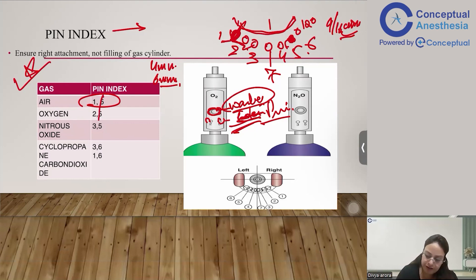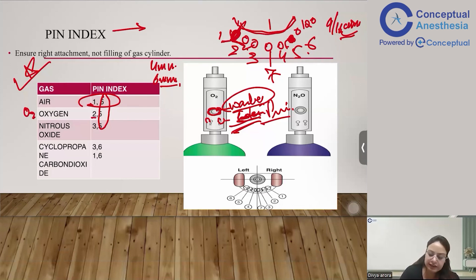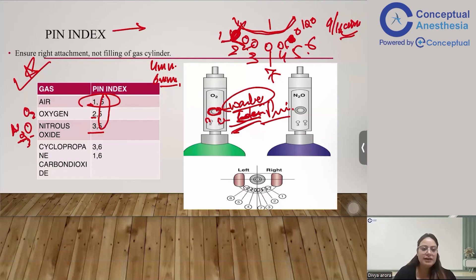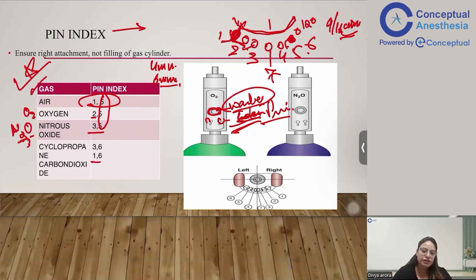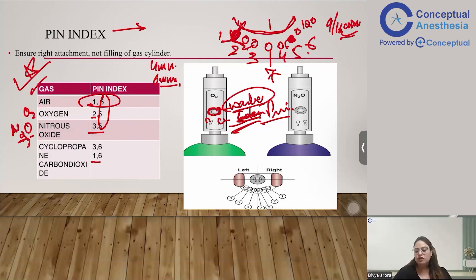A helpful mnemonic to remember the pin index: the number 5 is common to air, oxygen, and nitrous. Air has a single letter 'A' — so it's 1 and 5. Oxygen is written as O₂, so it's 2 and 5. Nitrous oxide is N₂O, giving 3 and 5. Additionally, cyclopropane is 3 and 6, and carbon dioxide is 1 and 6. The most commonly examined are air (1,5), oxygen (2,5), and nitrous oxide (3,5).